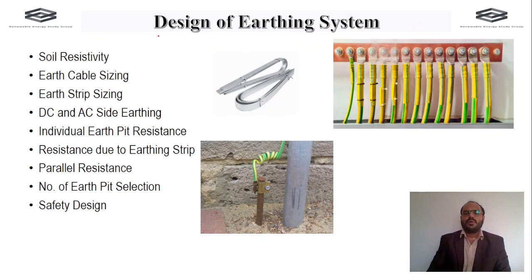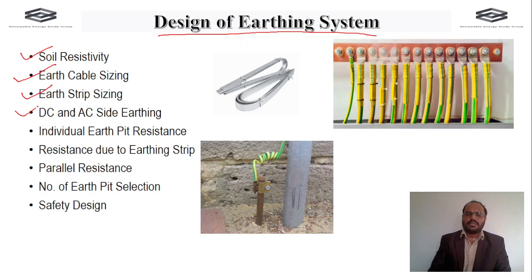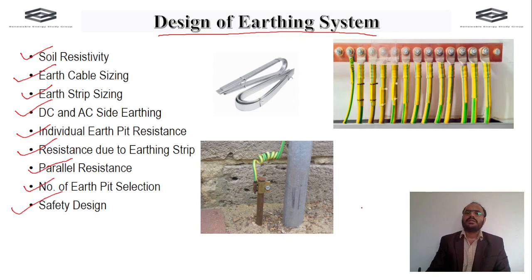We then discuss design of the earthing system, covering soil resistivity, earth cable sizing, earth strip sizing, DC and AC side earthing, individual earth pit resistance, resistance due to the earthing strip, parallel resistance, number of earth pit selection, and the safety design of the earthing system.